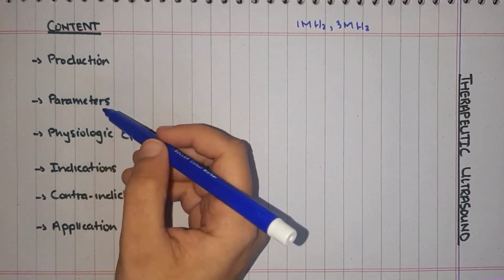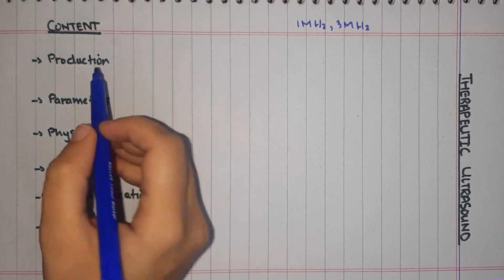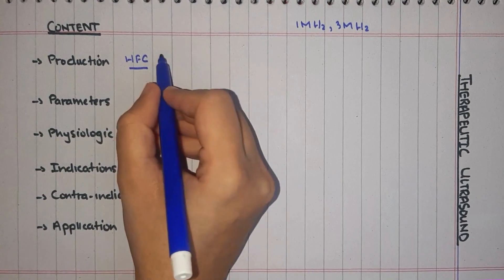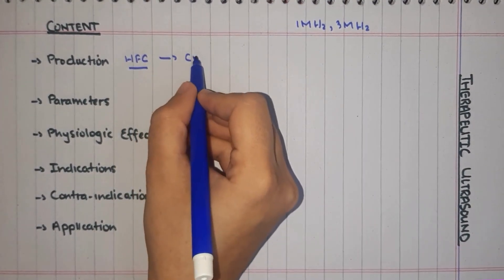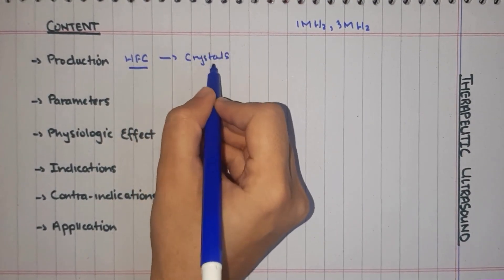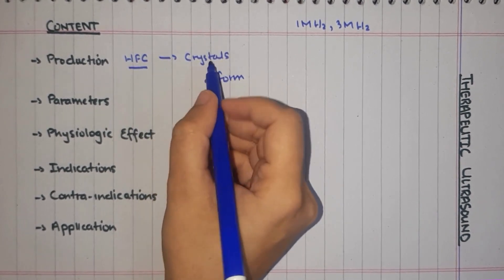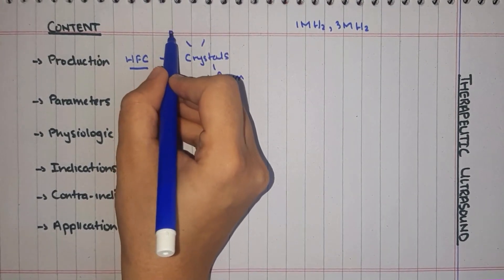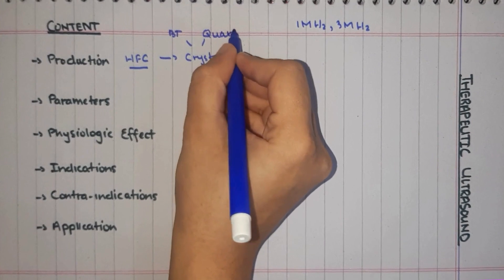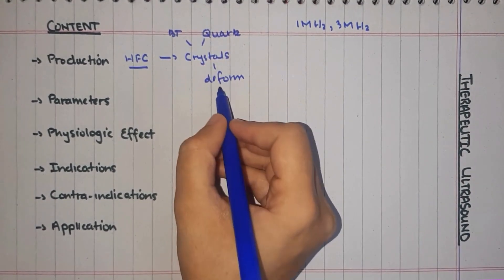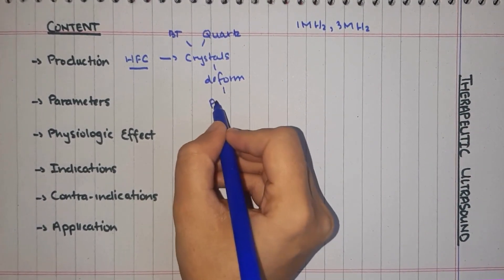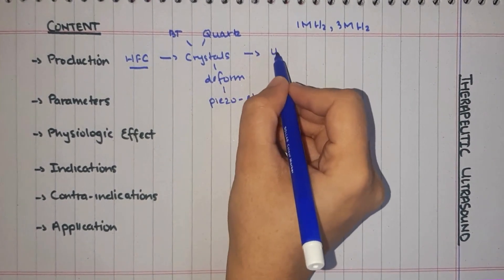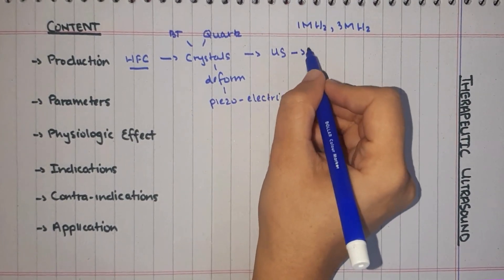First we review the production of ultrasound. We have a high-frequency current applied to the head of the ultrasound, which causes the crystals to deform. These crystals are either quartz crystals or barium titanate. The crystal deforms — meaning its shape changes — and this process is called the piezoelectric effect. As a result, the ultrasound beam is produced in a linear fashion.